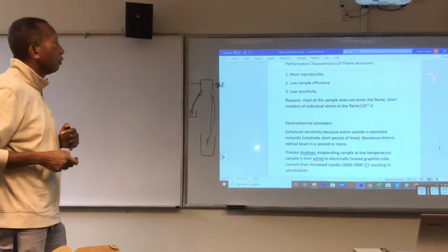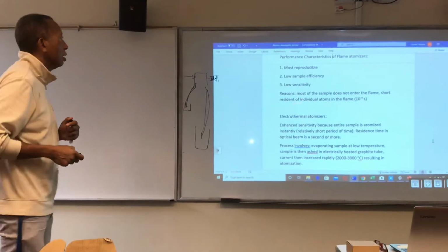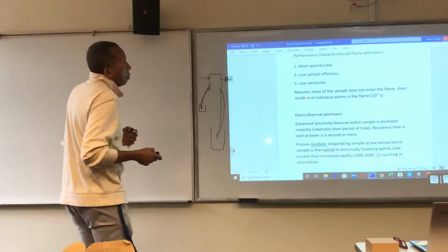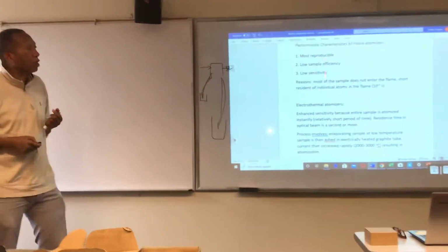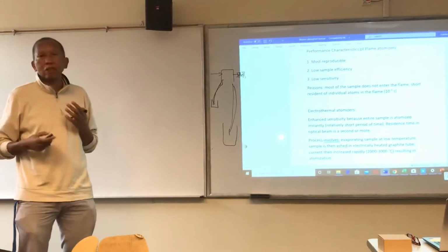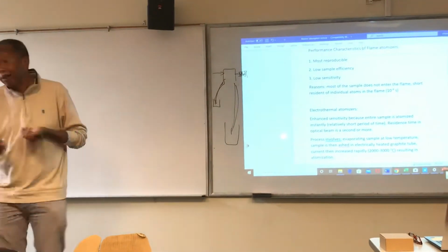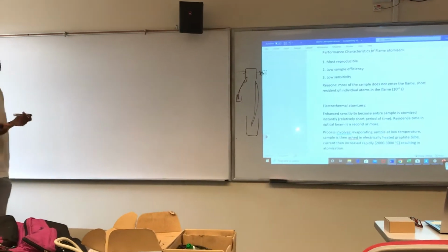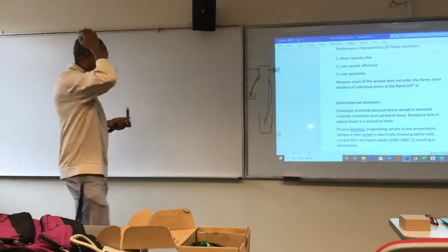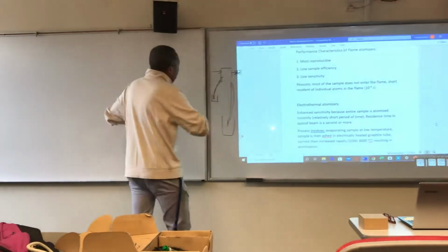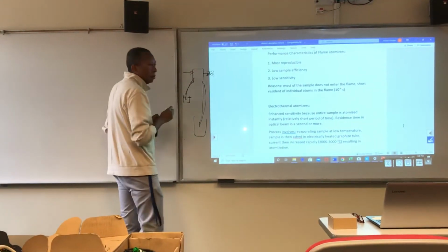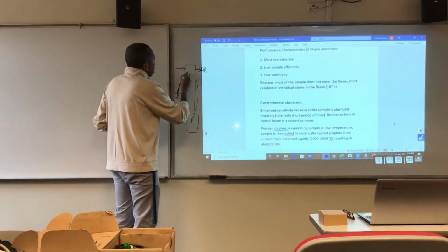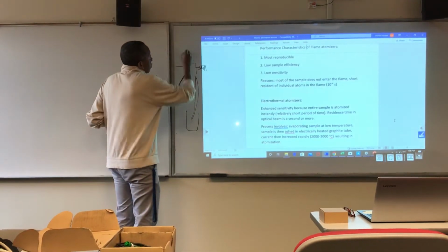But what is this idea of short resident time of individual atoms? What does that mean? You say there's a short resident time of individual atoms in the flame. And that's something like 10 to the minus 4 seconds. So it's really a very short amount of time.